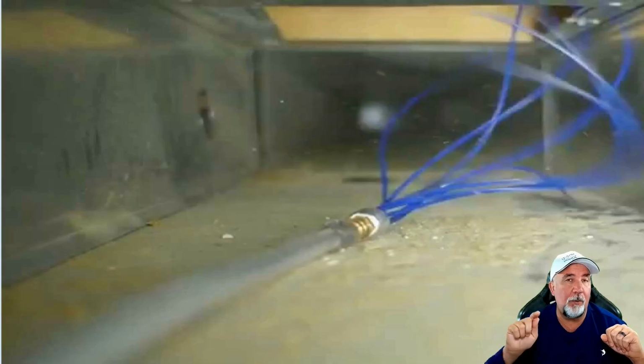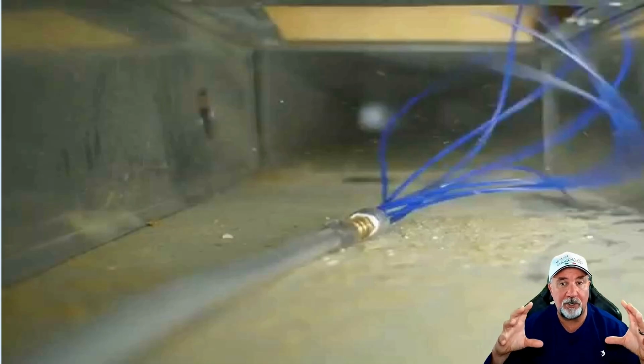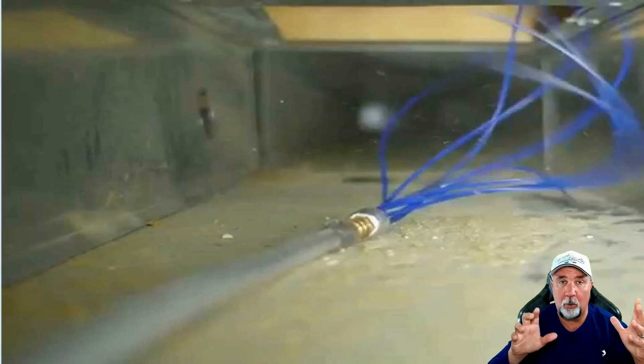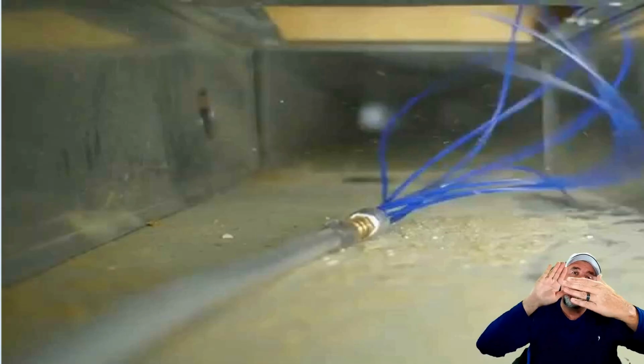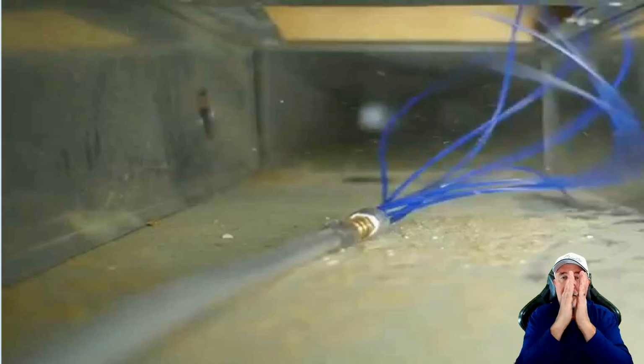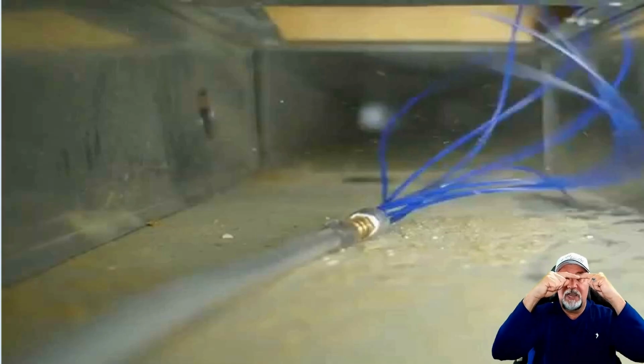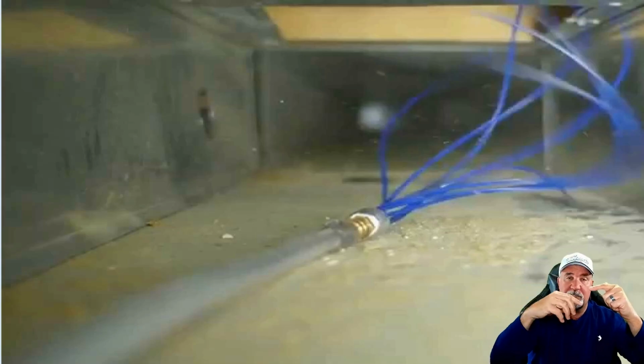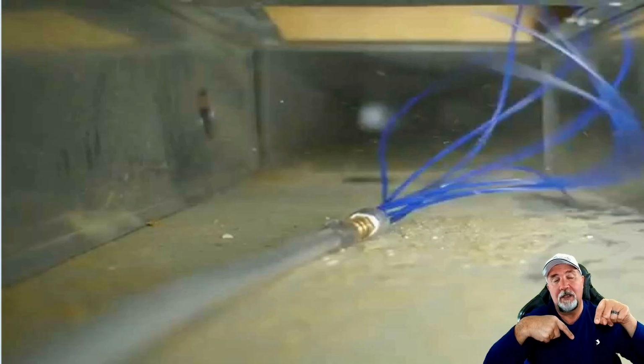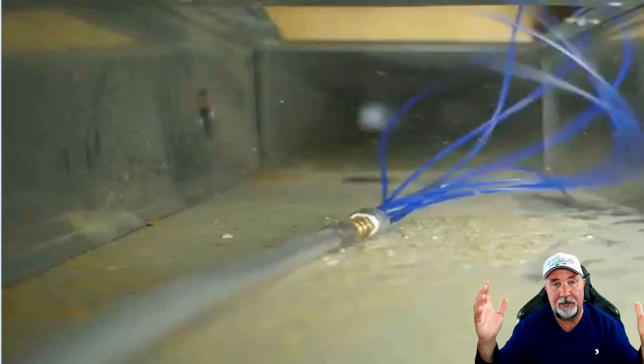But if you don't have a metal duct system, or your fiberglass duct, rigid duct board is not very sturdy, this thing whipping around can cause problems. I've seen it break holes where two pieces of rigid board were not properly sealed and there was a tape opening - that whip, as it was spinning around, whipped a hole in the tape and caused a bigger opening.